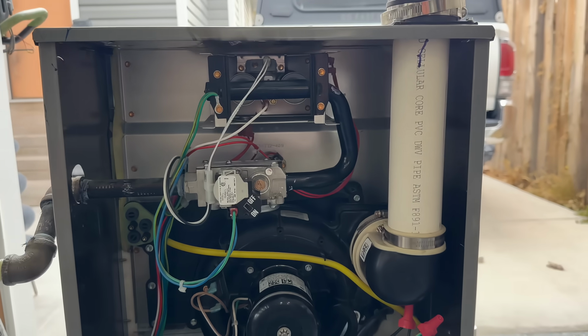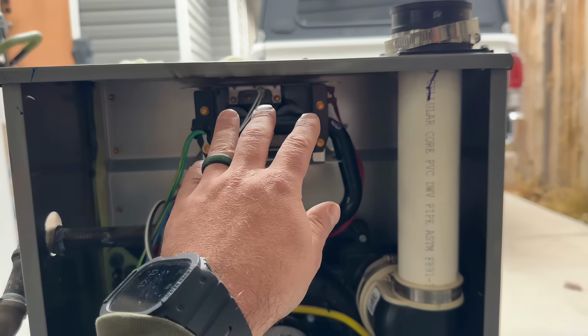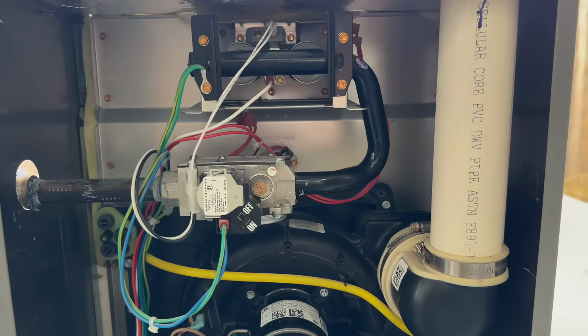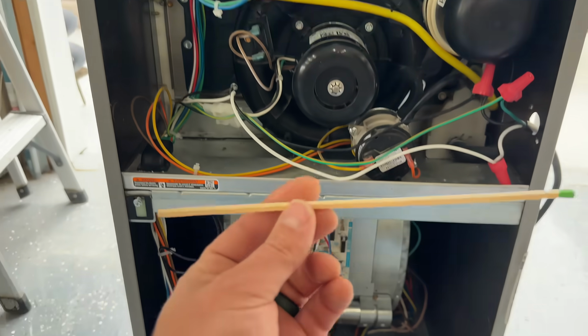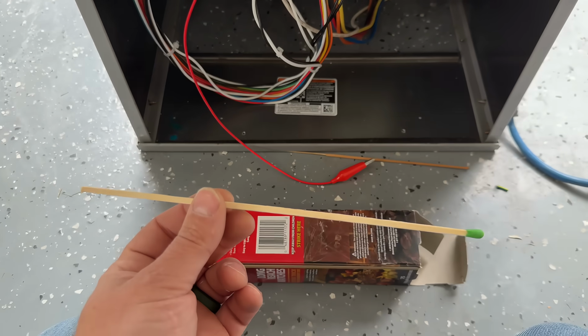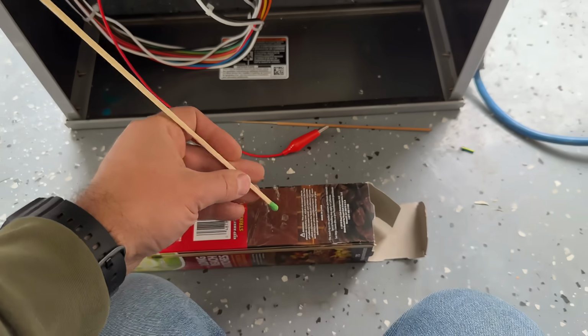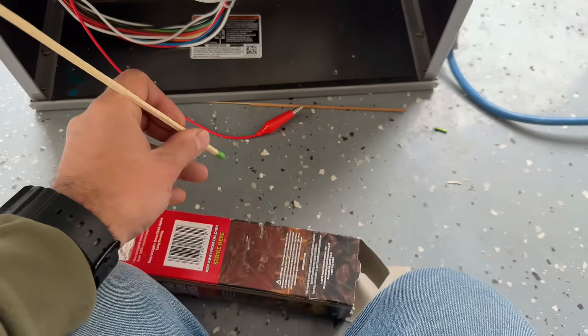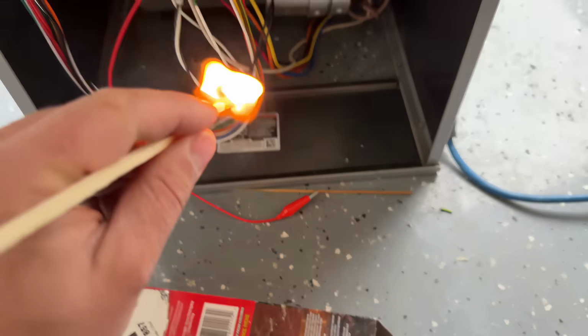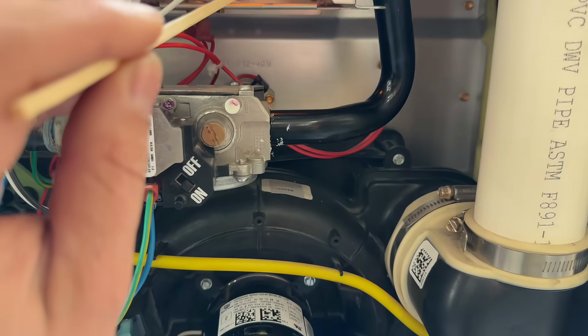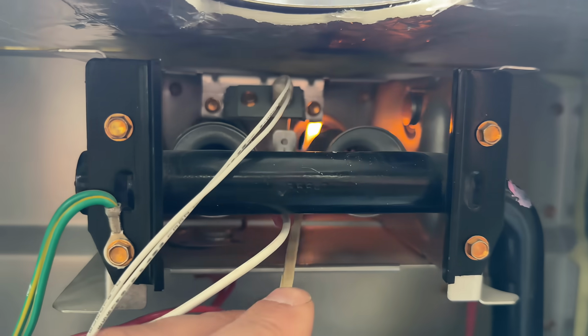Okay, so our first test just involved checking that flame as the blower motor comes on to make sure there's no orange. The second test is going to involve a matchstick like this one. So what we're going to do is light this and just demonstrate what we're going to do during this test. So we have our matchstick lit here. And now what we're going to do is just put this into the heat exchanger.